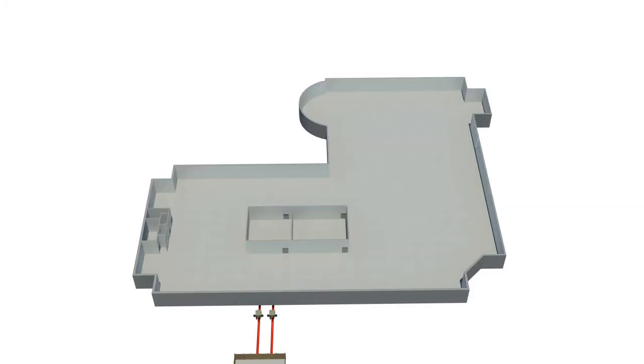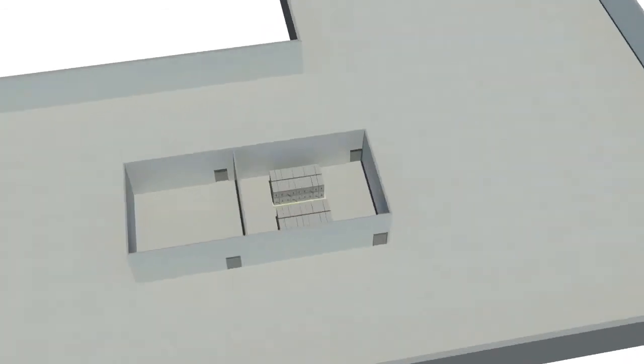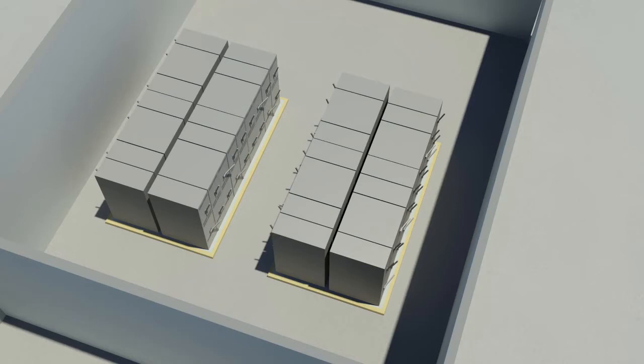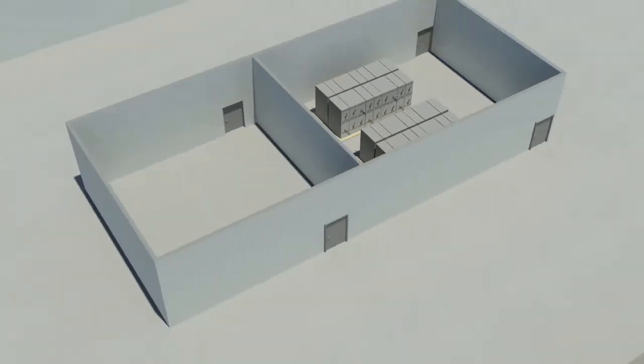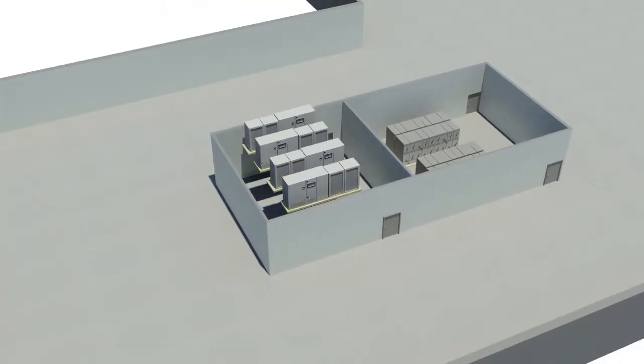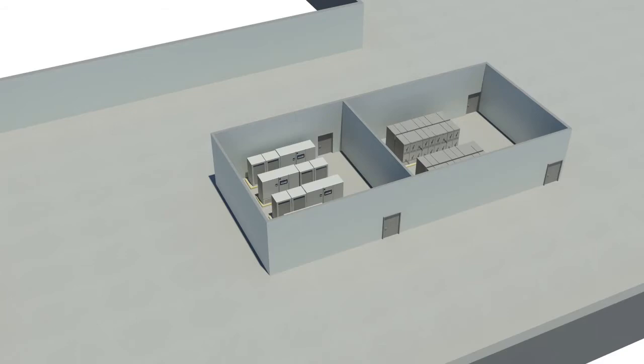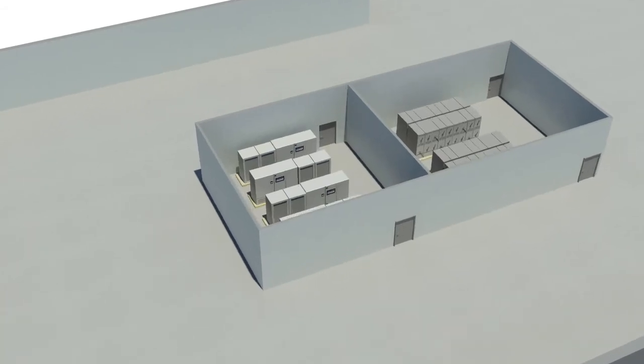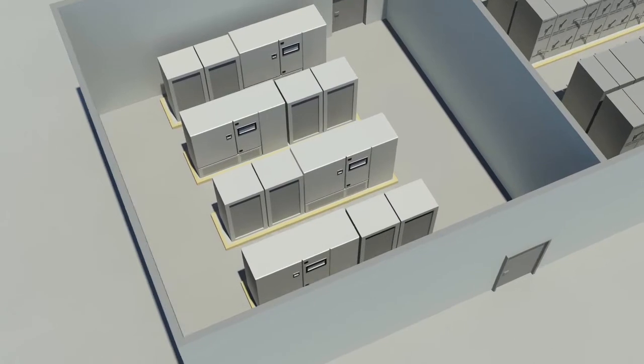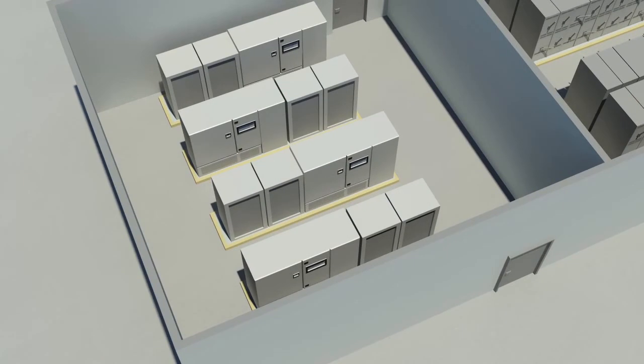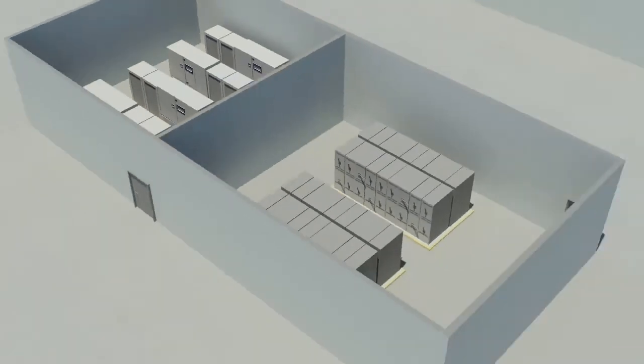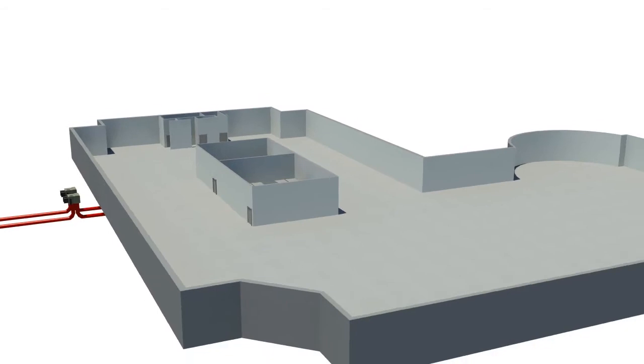All power sources transfer through redundant electrical switchgear, a system that manages a smooth transition of power between supplies as needed. The power is constantly fed from the uninterruptible power supply systems that can power the entire data center as the electrical load is being transferred from commercial power to generator. These layers of redundancy are how we ensure that power to the customer equipment is never absent, regardless of any emergency or unexpected power failure outside the facility.